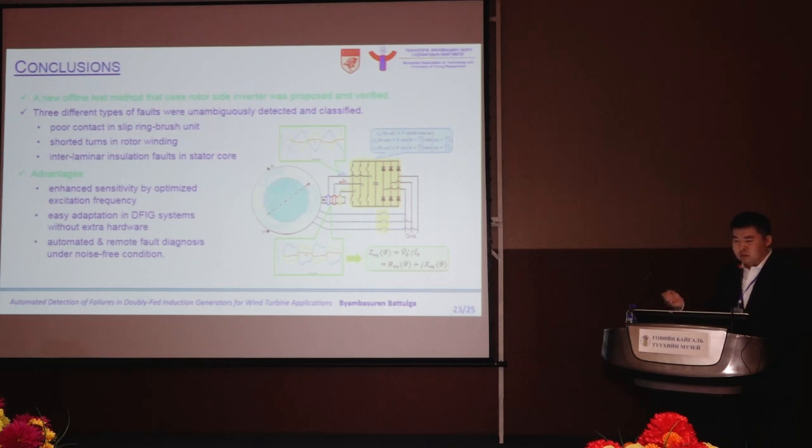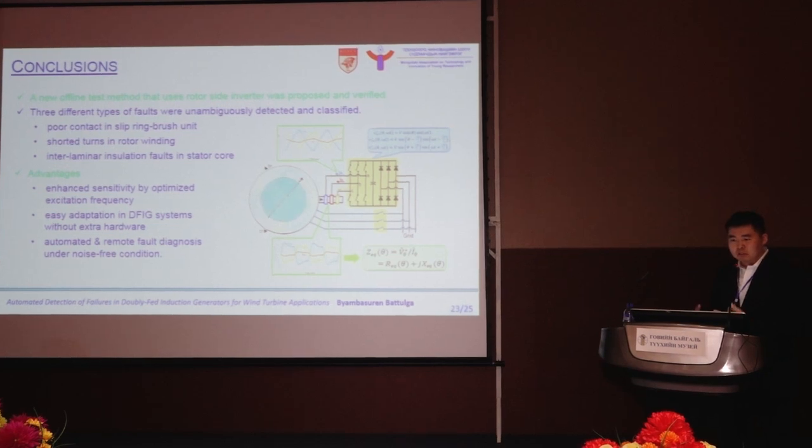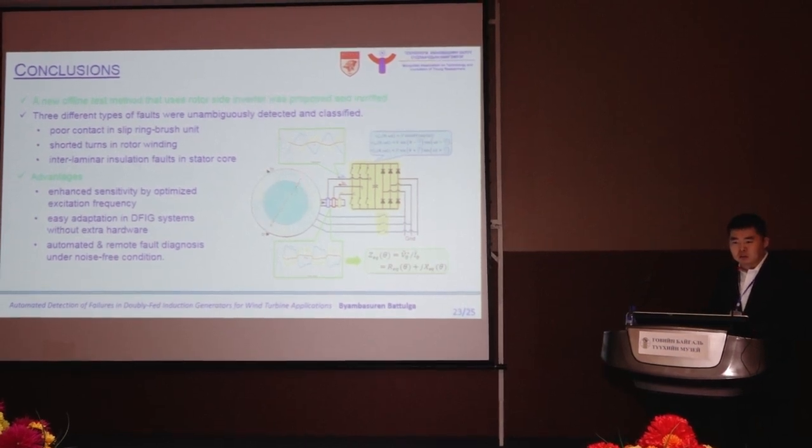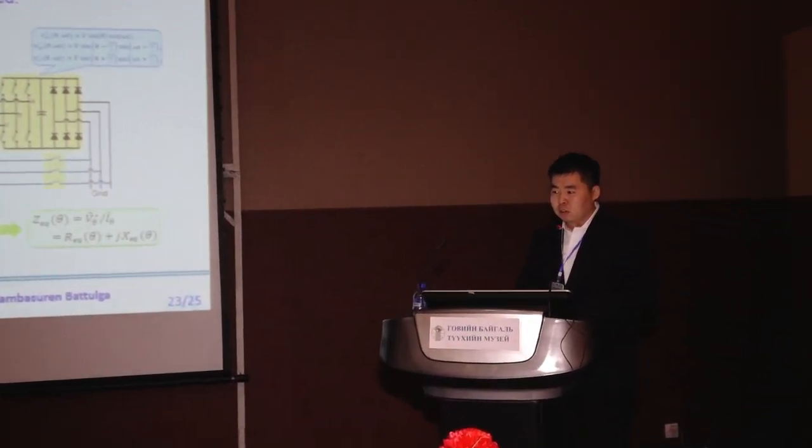Plot, as you can see, REQ and XEQ. From the pattern difference, we can identify whether it's healthy or not. Then we can also identify whether it's a rotor fault or a high resistance contact, or we can tell a stator core fault.